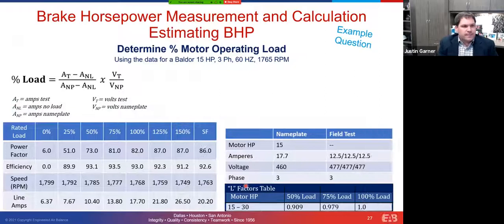So let's go into an example here. We've got some data down here that we collected out in the field. It's for that motor that we just saw the data for from Baldor. It's a 15 horsepower motor. Nameplate amperage is 17.7 amps at 460 volts, three phase motor. You can see we collected 12.5, 12.5, 12.5, so an average of 12.5 amps. Our voltage was an average of 477 volts.